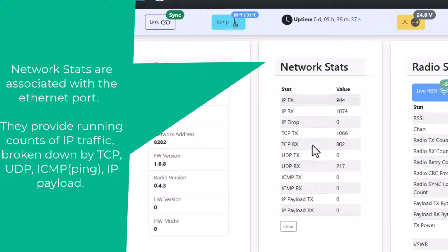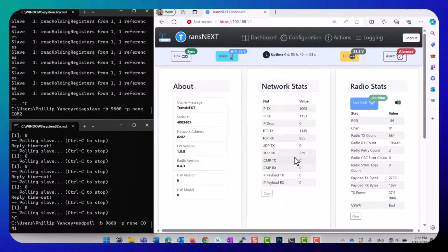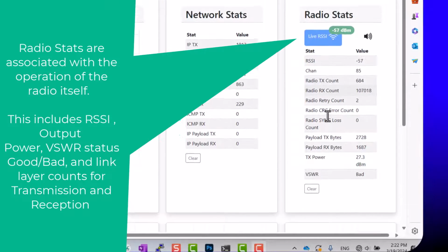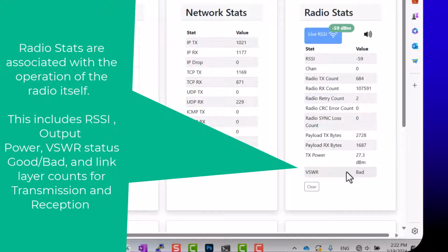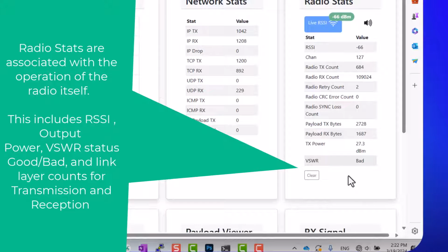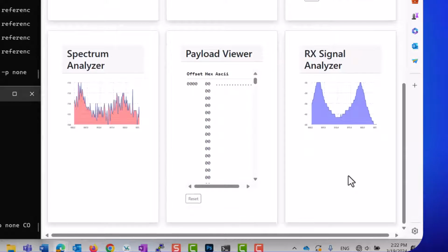We do have some IP information for the Ethernet port that I'm connected to. I believe over the air we are still very much doing serial broadcasts, and this is sort of proven by the fact that when I poll a remote, my COM port lights up on the remote that's not connected to anything. You can see here they've given us a lot of great information when it comes to RSSIs. You'll notice that I do have an alarm for VSWR, which is because I have an attenuator in line. So either it notices that, or potentially my attenuator is damaged from excessive usage.